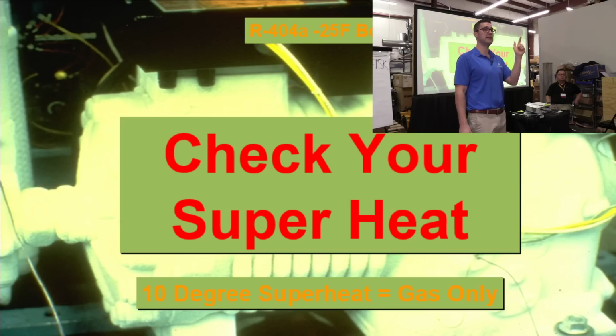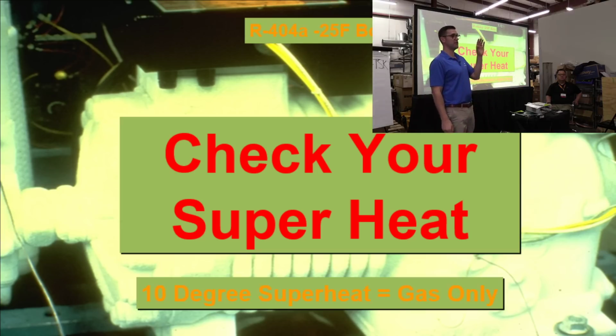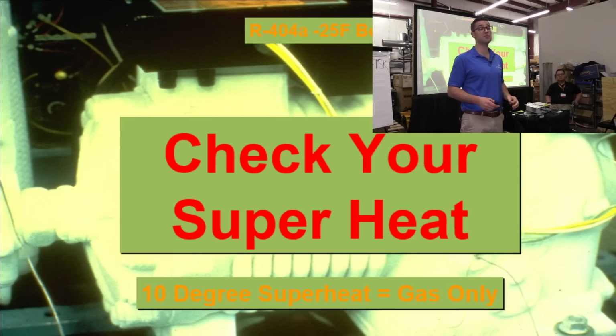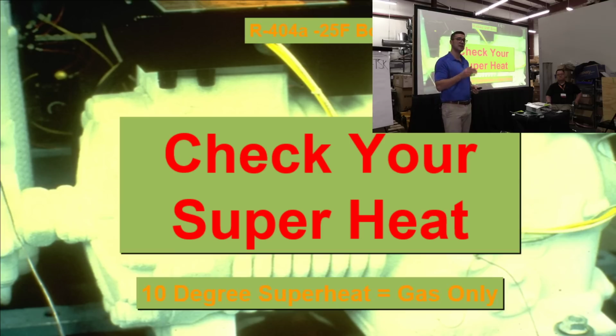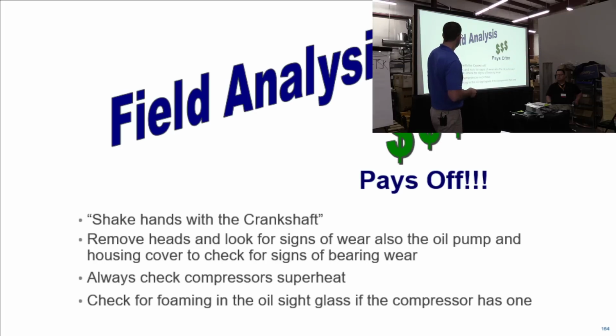100% dew point. Especially if you're working with glide refrigerants or blend refrigerants, you'll get yourself in a whole world of trouble if you pick bubble point. You think you have 10 degrees superheat. If there's 10 degrees glide, you could actually have 0 degrees superheat. So understand that you're using the dew point when you're checking superheat. Very important.